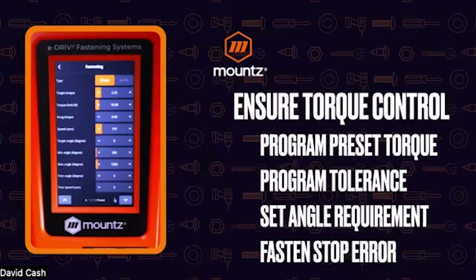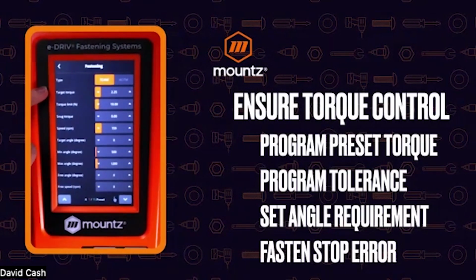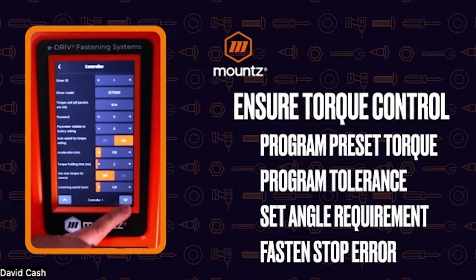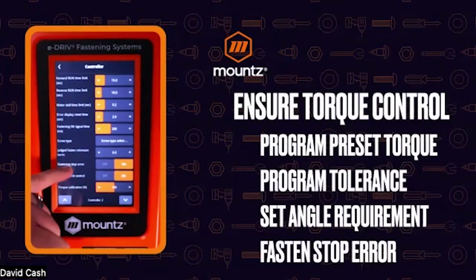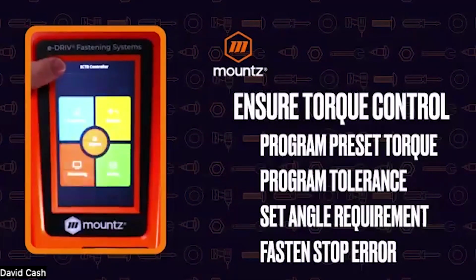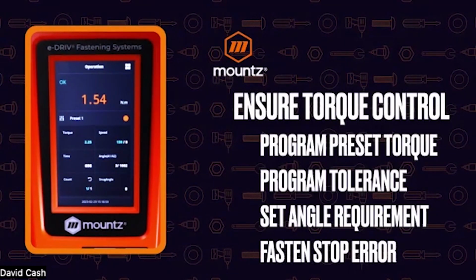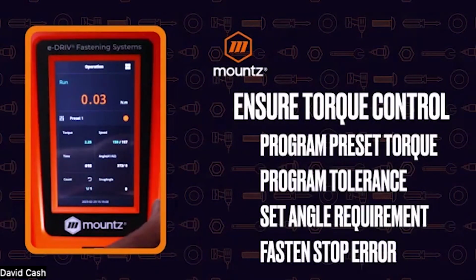The other thing that we can do is add an error that would generate if the operator lets go of the trigger of the tool before the system has fully completed its rundown. So you don't have a scenario where the operator doesn't complete a rundown because they let go of the trigger and just moved on. We can do that within our controller menu. We have our fastening stop error that allows us to set that. So if I turn that on, this will alert us if the driver is run without the actual completion of the torque. And if I go ahead and run the tool now and then let go, you can see the system generated a non-complete scenario.